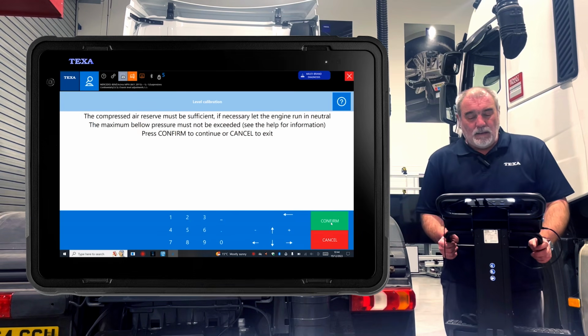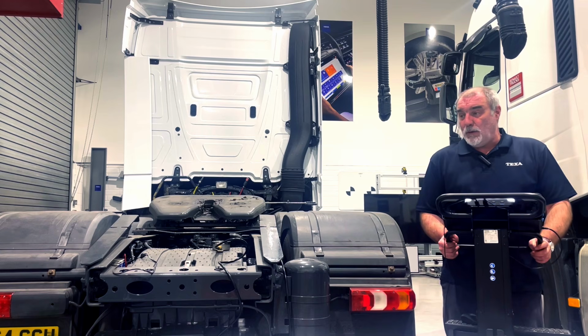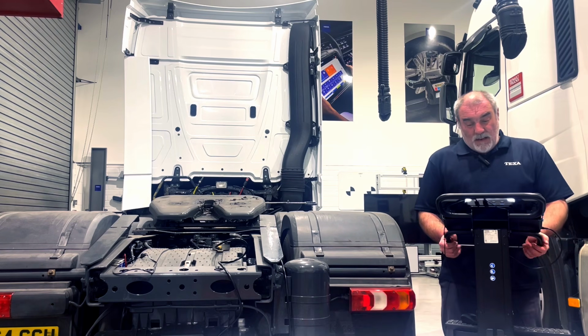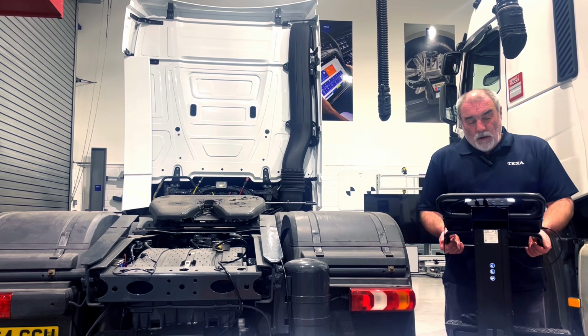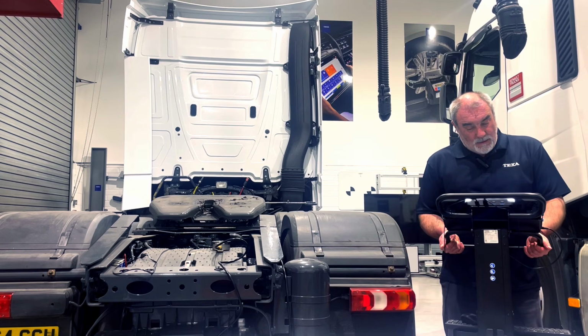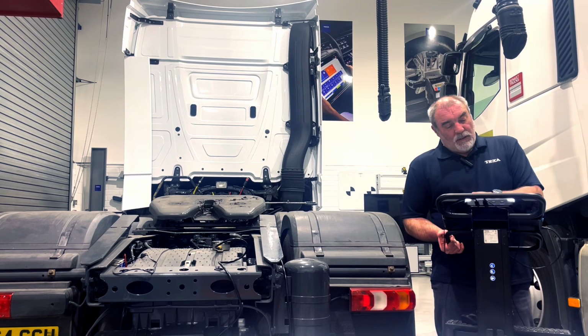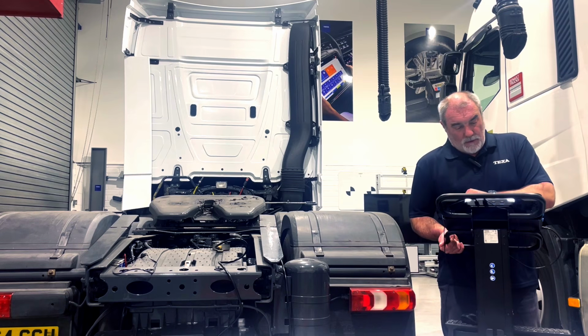By sufficient, they mean enough in there to carry out the calibration. If necessary, you can let the engine run. The maximum bellows pressure must not be exceeded. We can hit confirm again to continue. I know the pressure's up because I've just had it running.